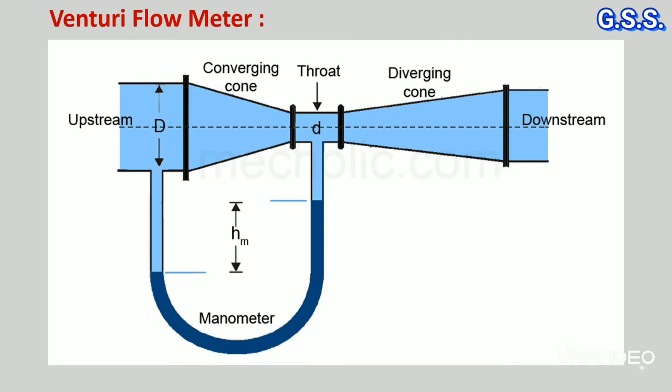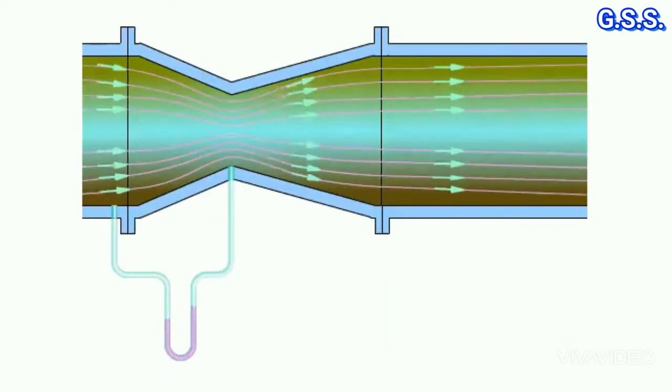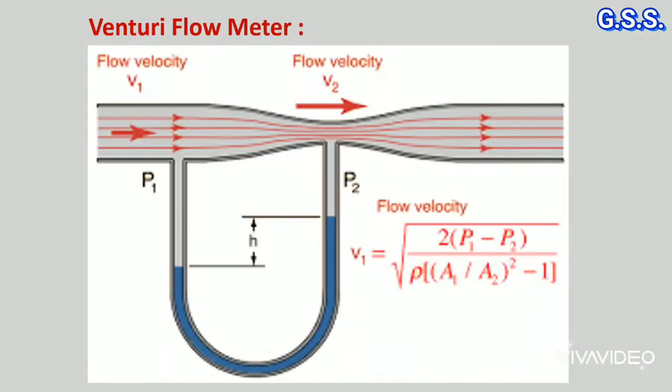Venturi flow meter works on Bernoulli's principle. In venturi flow meter, a converging and a diverging section of pipe is used. From the converging section to throat, velocity increases and pressure decreases. And from the corresponding pressure drop, volume flow rate is measured.